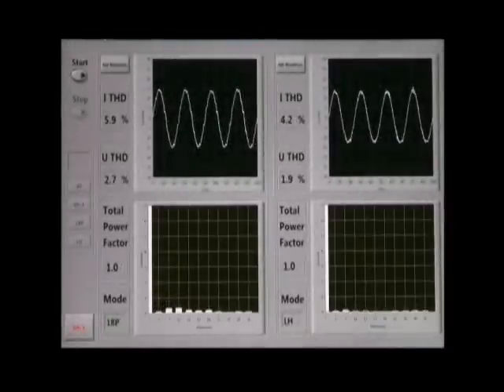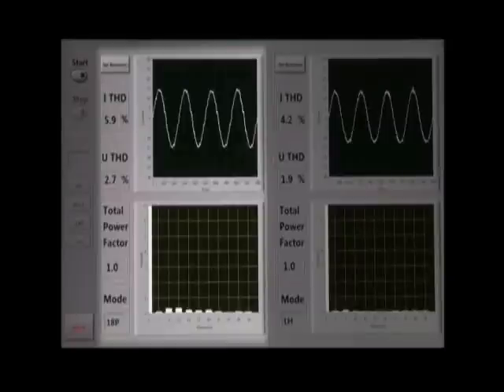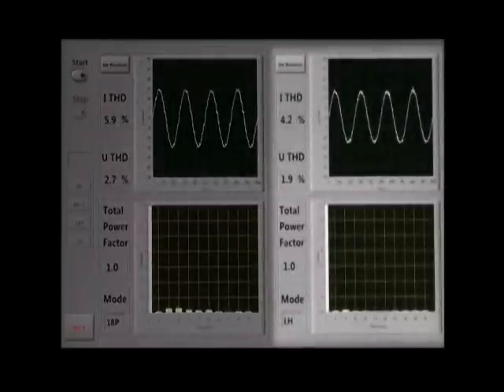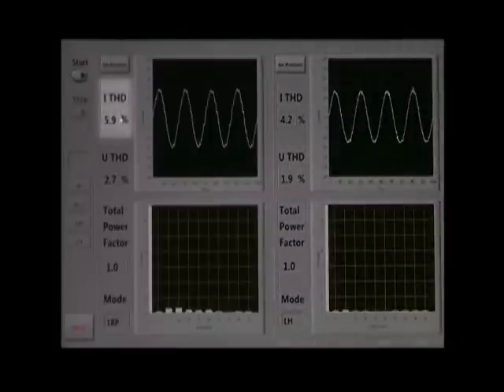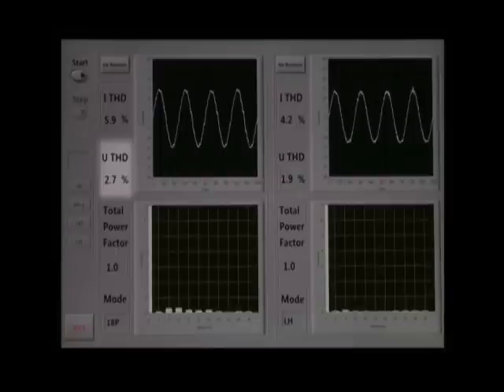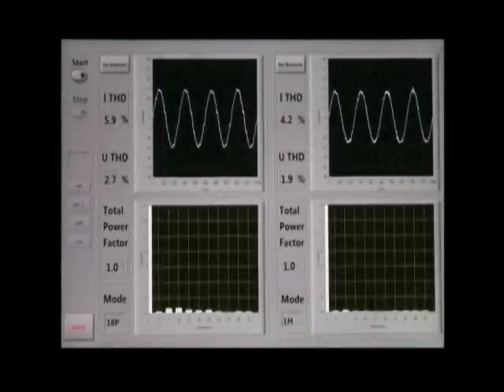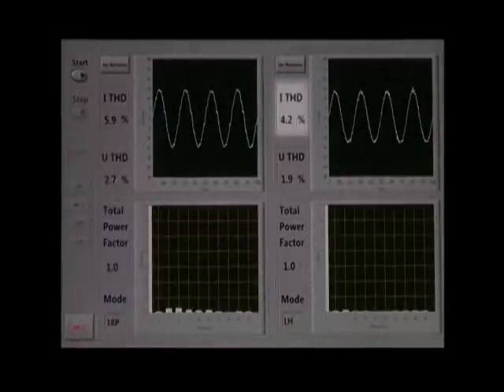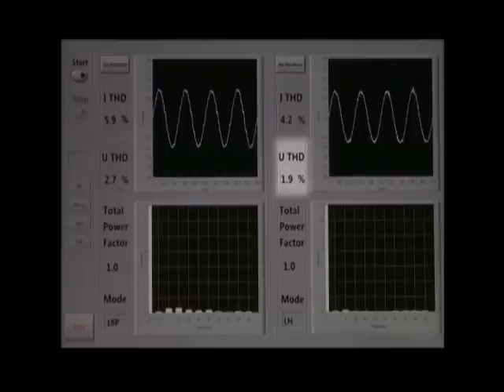And our final comparison is probably the most important, the comparison between a multipulse solution and the ULH. For our multipulse solution, I've captured an 18-pulse waveform and associated harmonic data, and I'm comparing that to the ULH waveform and harmonic data. On the left, the multipulse solution has provided us with about 6% current distortion and 2.7% voltage distortion. As I mentioned earlier, we are near unity in terms of the power factor. When compared to the ULH, we have 4.2% in terms of current distortion, and we're below 2% on the voltage distortion. Total power factor is at unity.